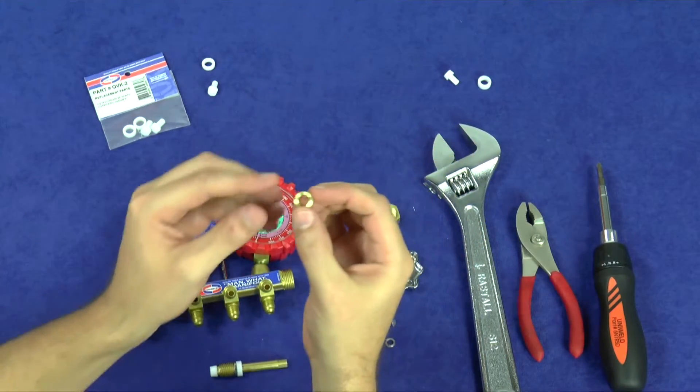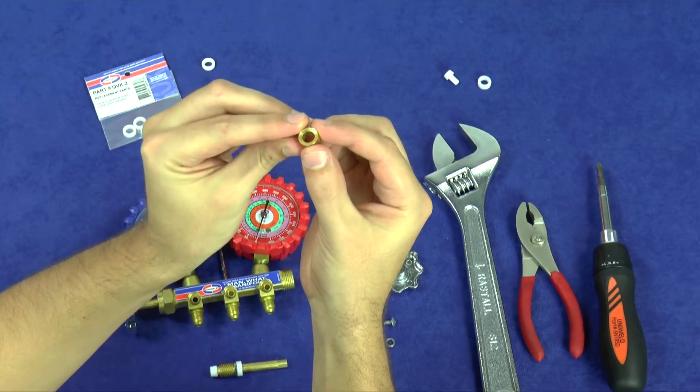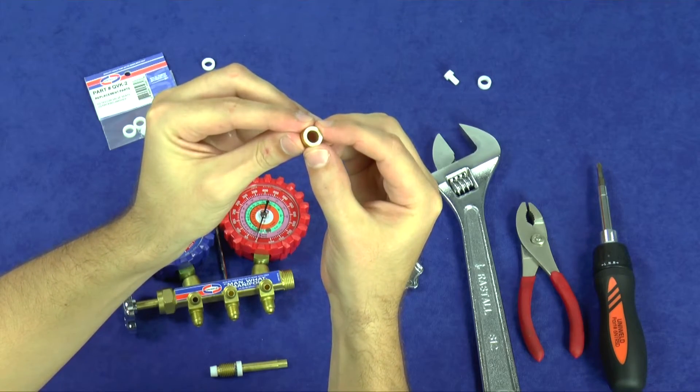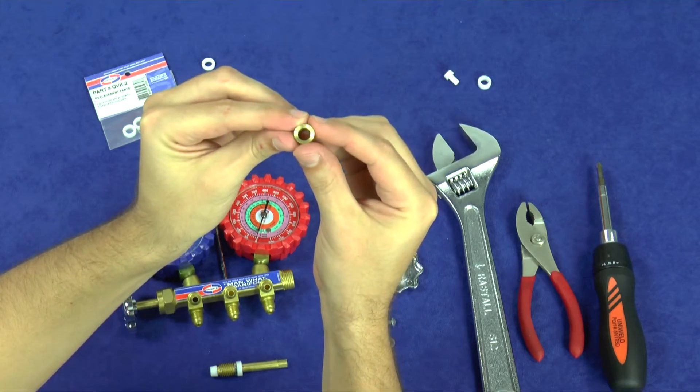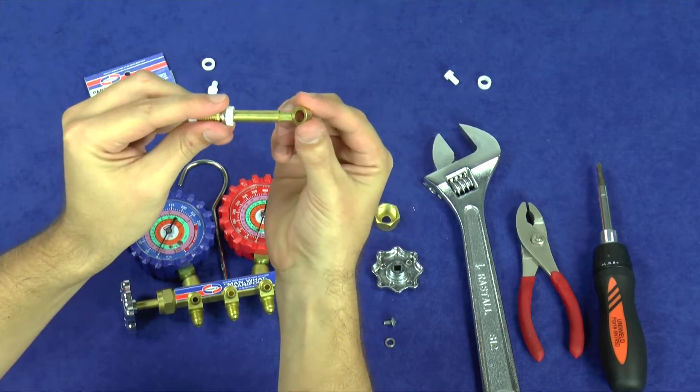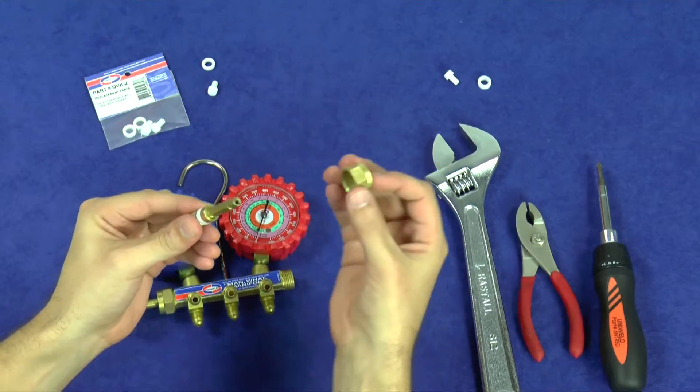Take note that the brass packing washer is tapered on one side. This design will compress the Teflon washer inward, allowing it to cold flow around the valve stem for a tight seal. Slide the brass packing washer on the valve stem with the tapered side facing the Teflon. Then replace the packing nut and metal hand wheel.